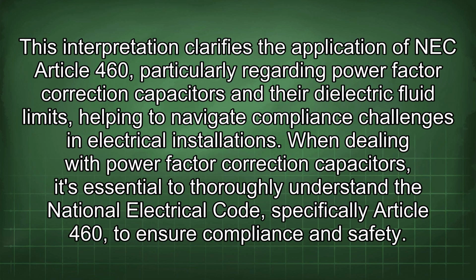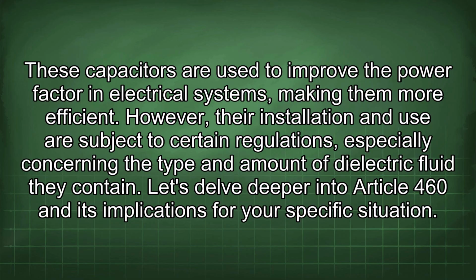This interpretation clarifies the application of NEC Article 460, particularly regarding power factor correction capacitors and their dielectric fluid limits, helping to navigate compliance challenges in electrical installations. When dealing with power factor correction capacitors, it's essential to thoroughly understand the National Electrical Code, specifically Article 460, to ensure compliance and safety. These capacitors are used to improve the power factor in electrical systems, making them more efficient.